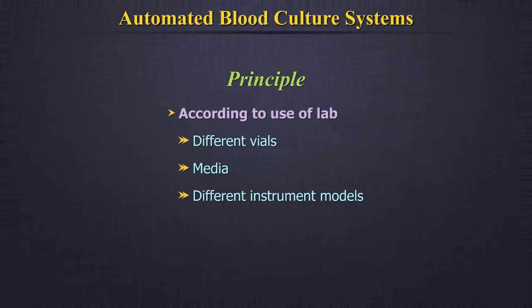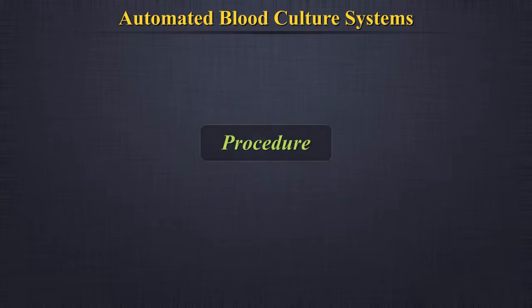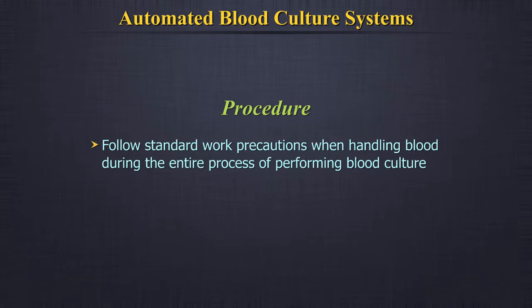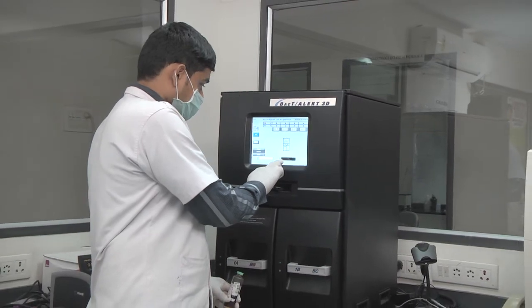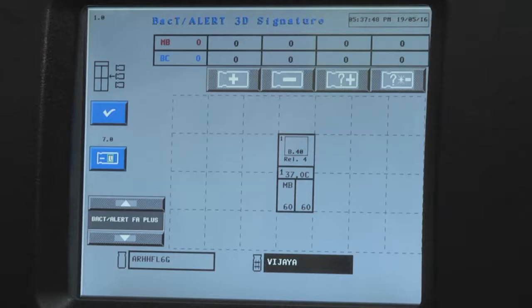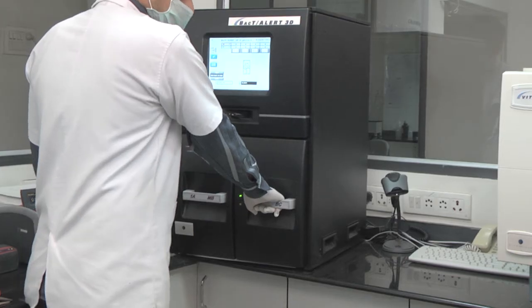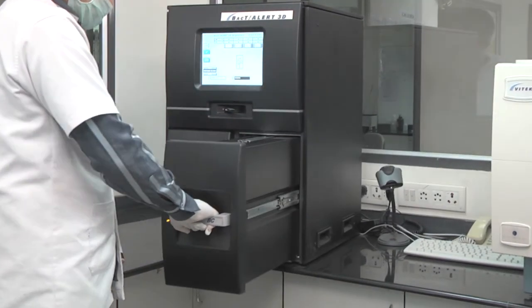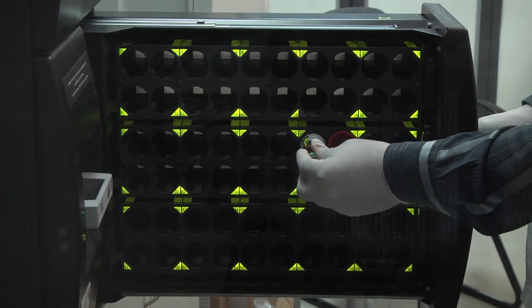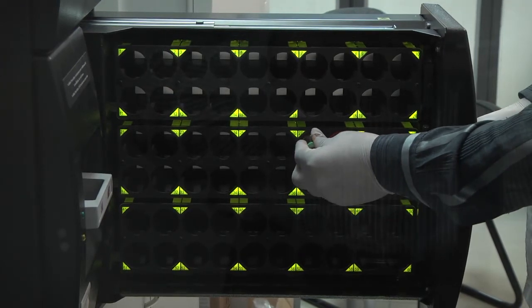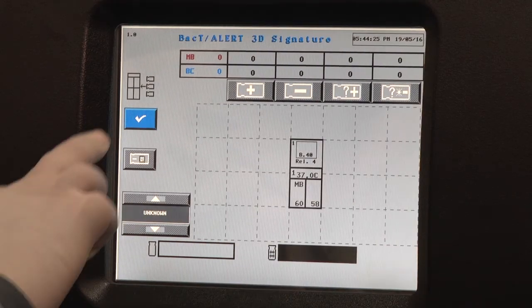Different vials, media, and different instrument models are available according to the use of the lab. Procedure. Lab personnel must strictly follow standard work precautions when handling blood during the entire process of performing blood culture. To load bottles, touch the load bottle icon, read the barcode of the bottle meant for loading, and type in the patient identification, sex, age, type of specimen, etc. as required. Open any of the drawers with green lights flashing and load the bottle randomly in any cell with a green flashing light. Close the drawer and touch the tick mark on the monitor.